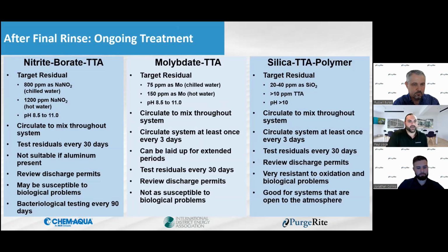All right, so we did all that. You decided, hey, I'm going to get this up within 2 weeks. What treatment am I going to use, right? So you have 3 basic, common treatment strategies throughout water treatment. You have your nitrite azole-based one, which does really well, especially in closed heating hot water loops with the temperature. It stands up a little bit better to that.